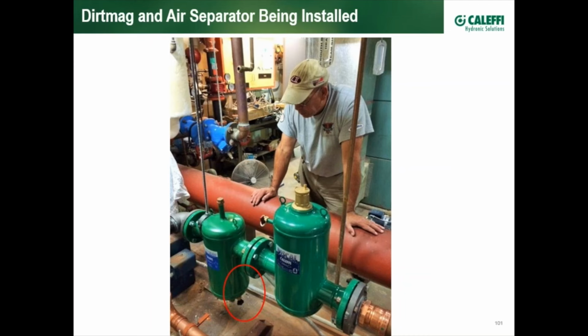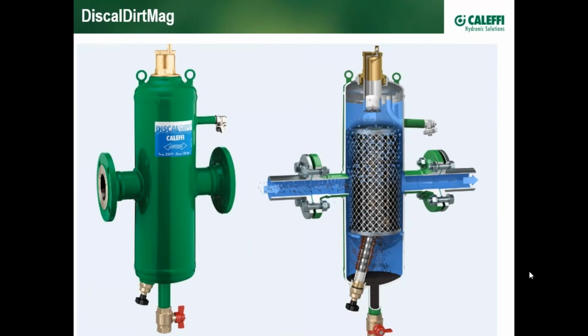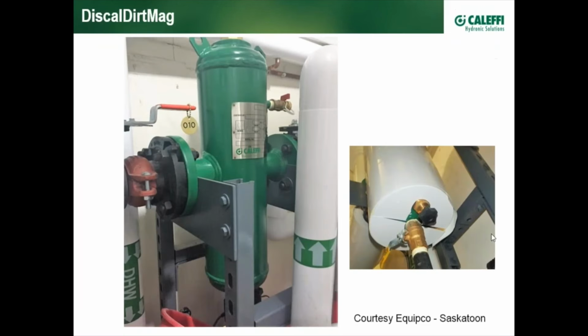And the answer is, well, yes. After those contractors had installed those previous two jobs I just showed, Caleffi introduced the Discal Dirt Mag in 2015. The upper portion of the 2-in-1 device has the same efficiency as a dedicated air separator, and the same efficiency in the bottom portion as a dedicated dirt separator. Here's an example of one in installation sent from Saskatoon.